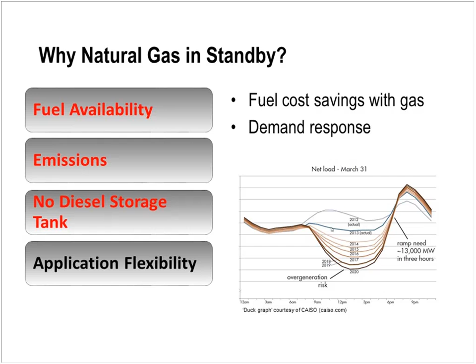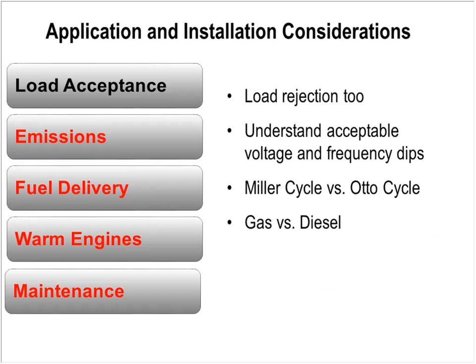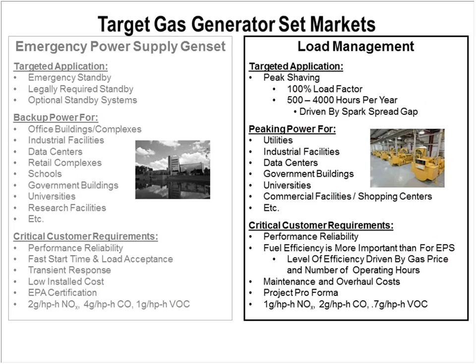Load acceptance - gas engines are now capable of picking up quite a bit of load. 25% block load is not uncommon, and load rejection as well. There are a number of different methods we can use, and gas engines can do that very effectively. In these load management applications, they're designed at the 100% load factor, upwards of 4,000 hours a year are not uncommon, and 1 gram NOx would be the standard setting on those engines.